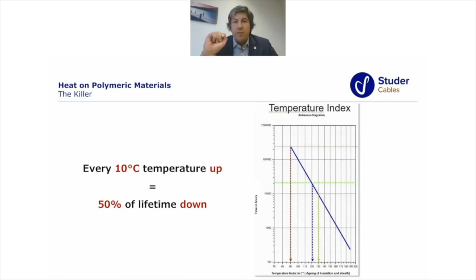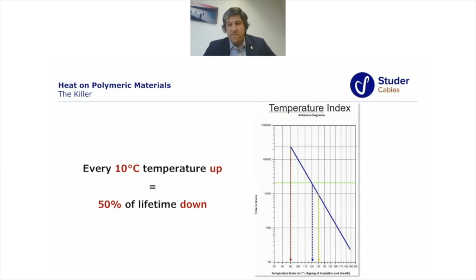In the polymeric materials we use, the typical Arrhenius curve shows that at a temperature of 120 degrees, the polymeric material would be able to withstand 20,000 hours. If I increase the temperature by 10 degrees, immediately it drops by 50%, down to 10,000 hours. This is very important because heat caused by resistance in PV is a very frequent phenomenon.